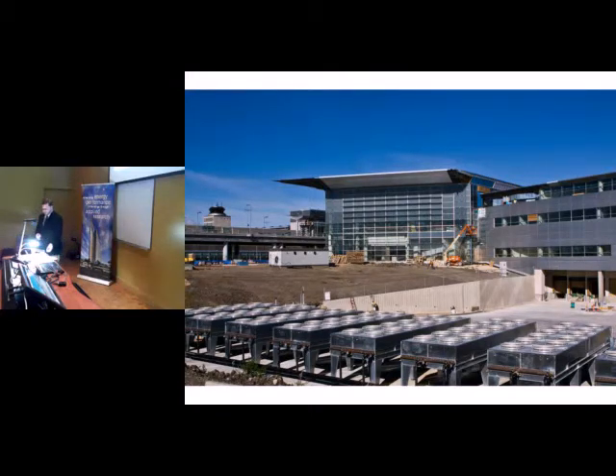We found that we actually had to dial the radiant floors down quite a bit in order to make it comfortable for people to stand in spaces, because it was just such an intense amount of heat that these very, very large areas of floor were producing. The worst case was in the passenger security clearance area, where people are waiting in line to go through the security gates. And you could be waiting 10, 15, 20 minutes, depending how long the lineups are there. And we found that particular area, because of the ceiling height being so low and the radiant floor being right there, fully exposed on tile, it made the place actually uncomfortable, so we had to turn that floor down quite a bit. That we did not expect to have happen.